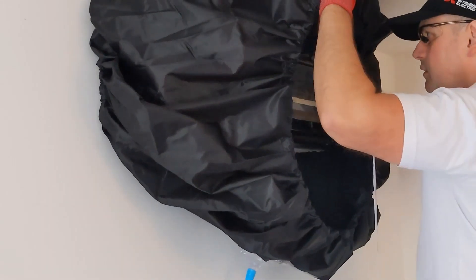At the same time, this is an opportunity to look at the state of that coil. Throughout, I'm going to be checking the state of the coil, and I'm also looking for any oil residue or anything like that to give me any inclination if there are any leaks.